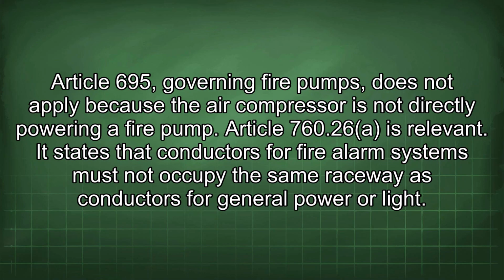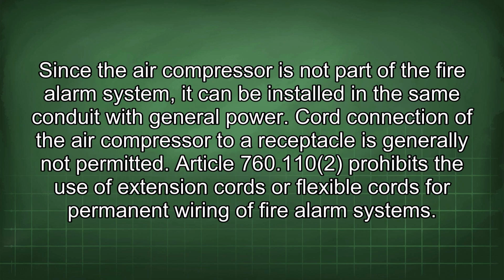Article 695, governing fire pumps, does not apply because the air compressor is not directly powering a fire pump. Article 760.26 is relevant. It states that conductors for fire alarm systems must not occupy the same raceway as conductors for general power or light. Since the air compressor is not part of the fire alarm system, it can be installed in the same conduit with general power.